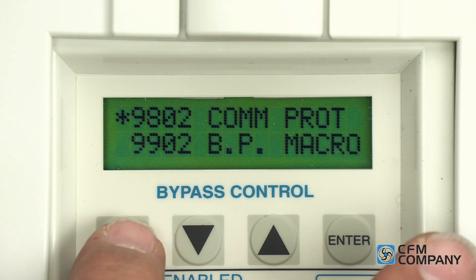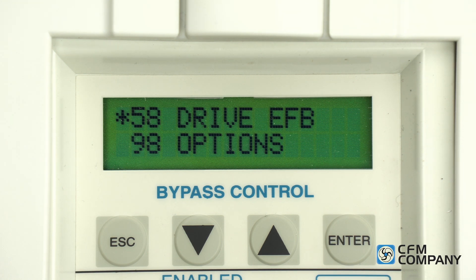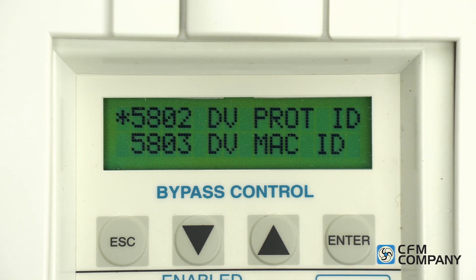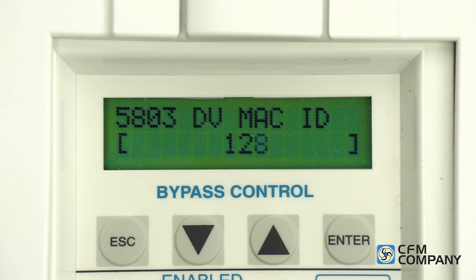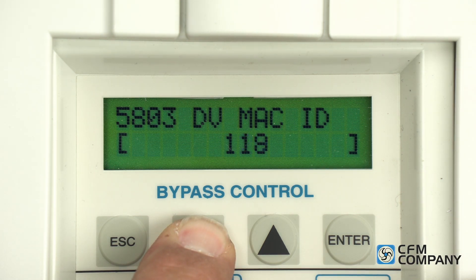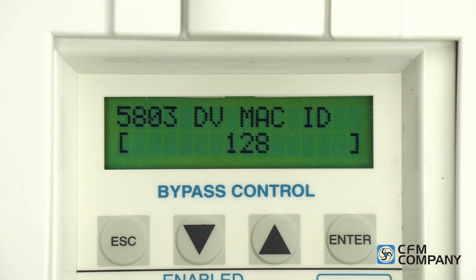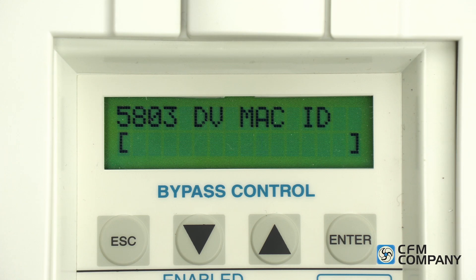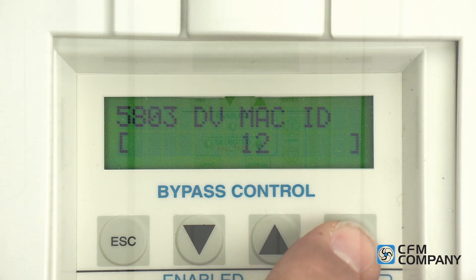To program the drive MAC ID, press escape to exit group 98. Press the up arrow to highlight group 58 drive EFB and press enter to select. Use the down arrow to highlight parameter 5803 dv MAC ID and press enter to edit. Use the down arrow to decrease the value. A long press of the down arrow will change the cursor from ones to tens place on the display. A quick shortcut to change the MAC ID value to 1 is to press both the down arrow and the up arrow at the same time — the value will instantly change to 1. Then press the up arrow to increase the value. Change the value to 12 and press enter to save.